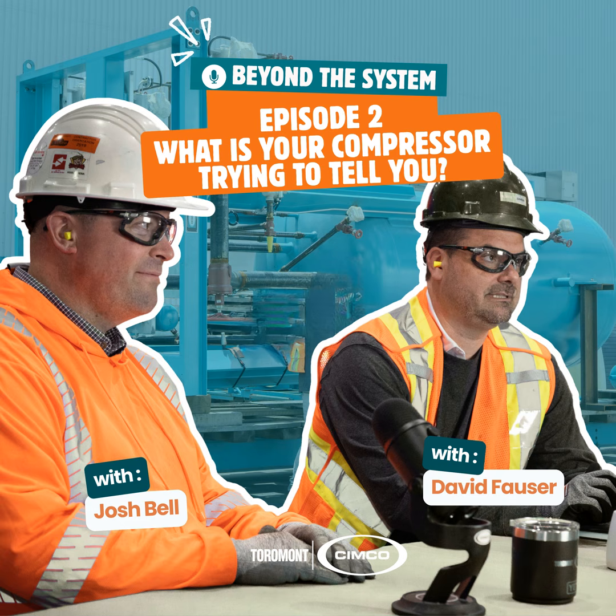Maybe one belt's broken. If you're using your reciprocating compressor and it's belt driven, often at different stages your belts will react differently, but under full load they should be tight. It should be quiet, down to motor noise, and then also monitor your motor.